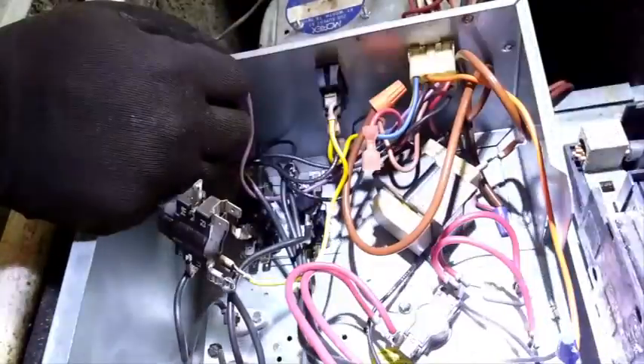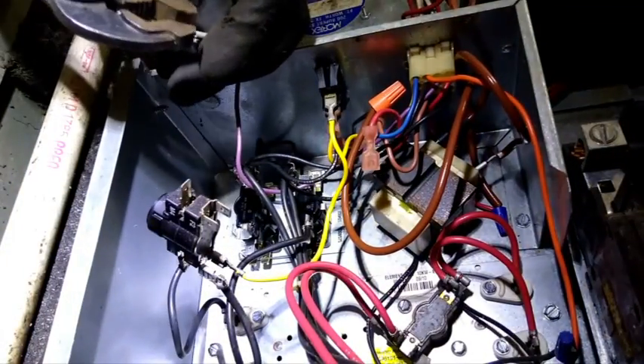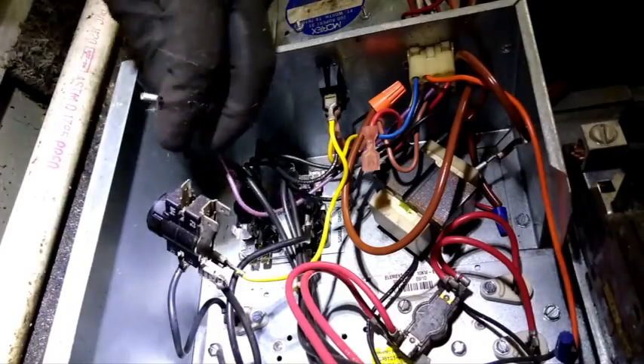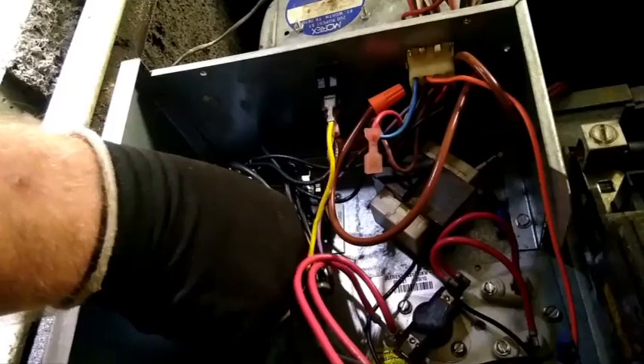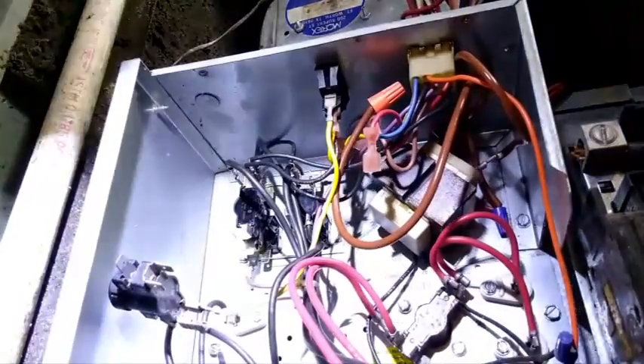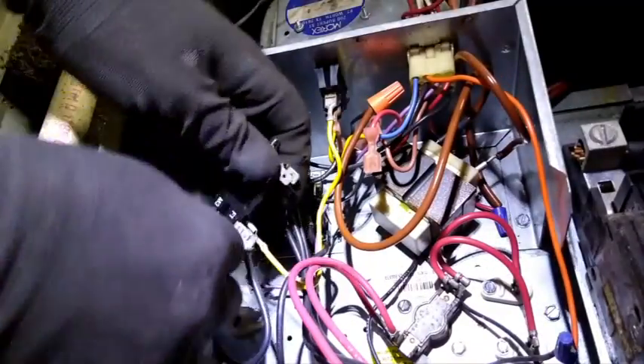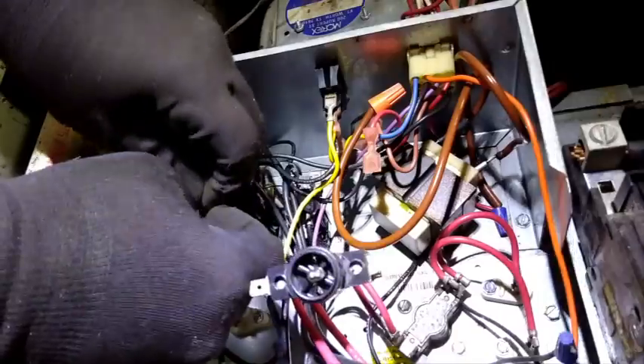If you get a loose terminal, see there's a sequencer right there. The disc is missing off the bottom of it. Most of the guts fell out of it. I see burnt terminals all the time because they get loose and then it gets warm because the connection's not good, then they burn the wires off. So you want to check. Electric furnace, more than anything else, you need to check the tightness of the wiring when you're doing preventive maintenance on them. If anyone ever does preventive maintenance on one, that's what you would do.